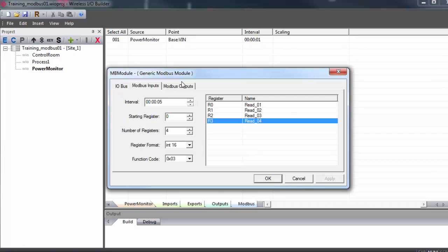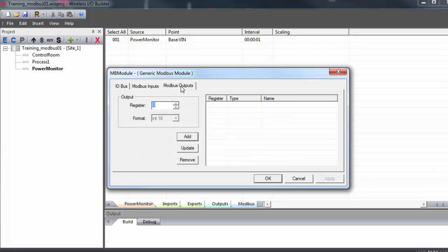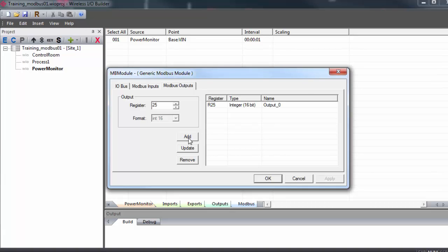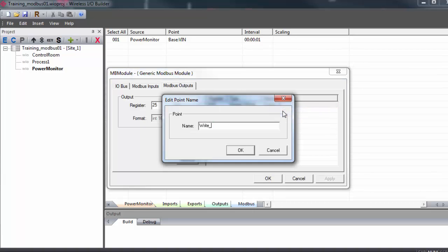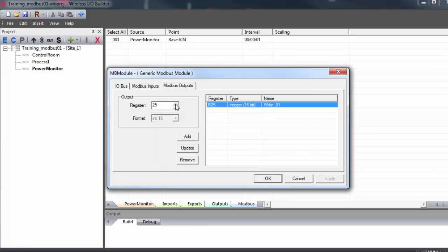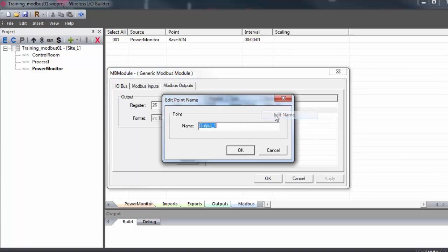Now I'll move on to the Modbus output tab. And this is where we can specify registers in the Modbus slave that we want to write to. You give the register address you want to write. Again, remembering that register 0 corresponds to the first register in the slave database. I'm going to grab the word at register 25 on my power monitor. Once you have the register set, you can click add. The write command will show up in the window. I'm going to go ahead and give them a name since output 1 is pretty generic. And I'm going to grab 26 as well and give that a name.